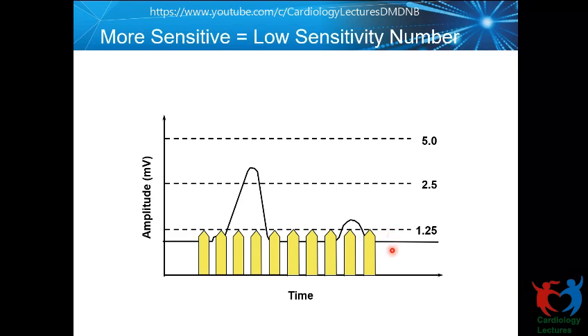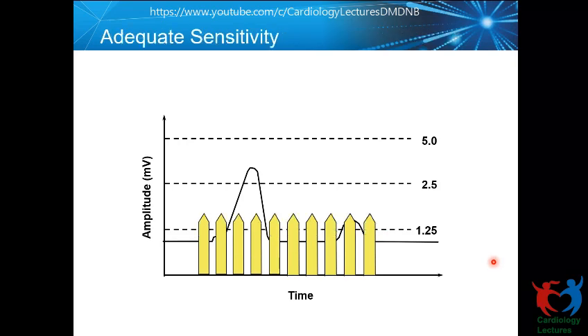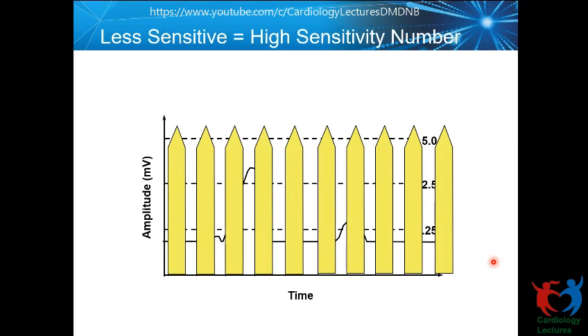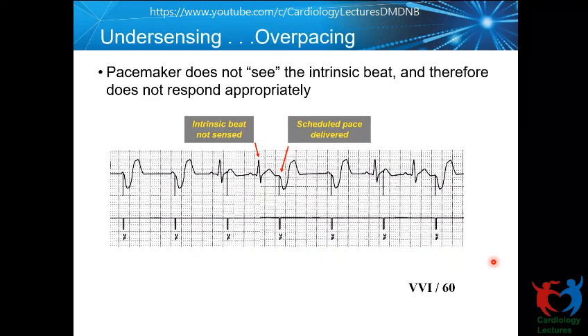The lower the value, the higher the sensitivity. Higher sensitivity might expose the patient to oversensing, and you want optimal sensing. And when you program a higher number, you're making the sensitivity low, so the pacemaker may not sense adequately. An example of undersensing is where the R wave is not sensed and it ends up pacing, and it might end up pacing on the T wave, which could be dangerous in a patient that's vulnerable to getting ventricular tachyarrhythmia. And the opposite is also true, which is oversensing.